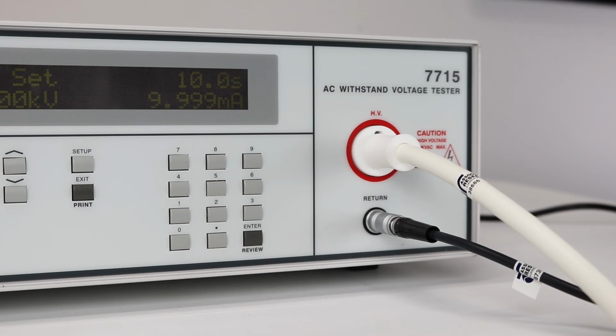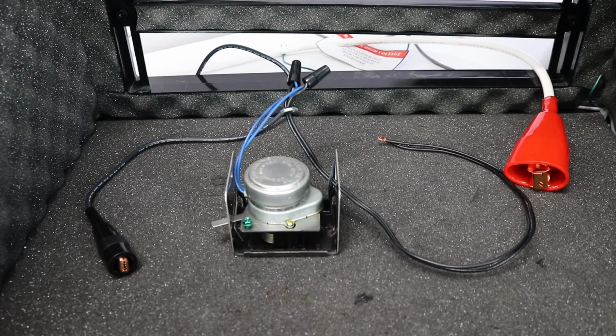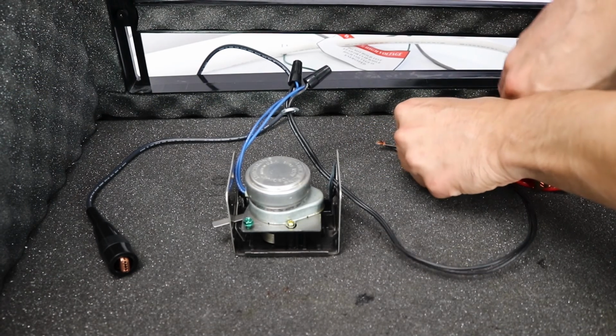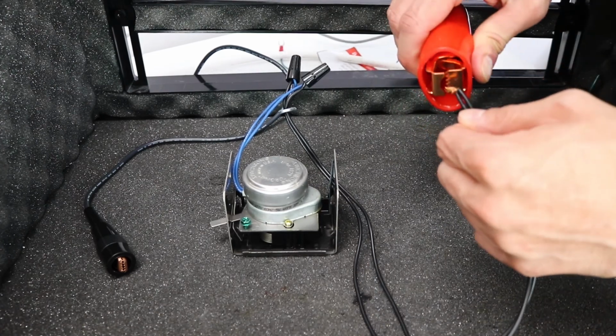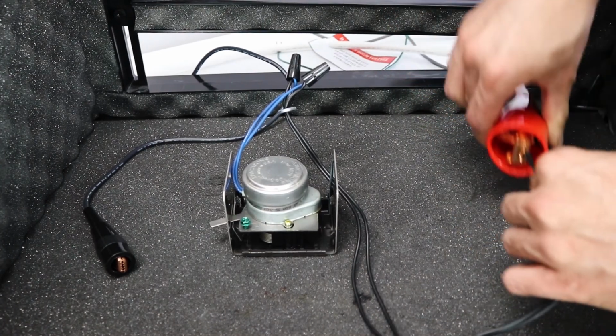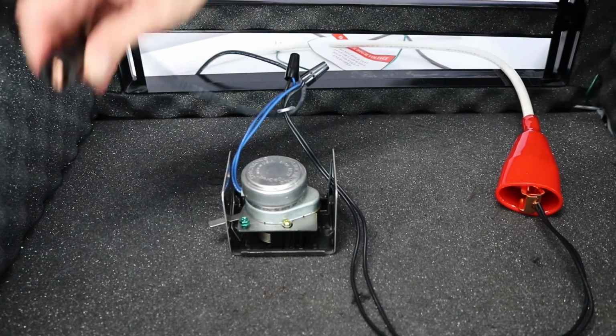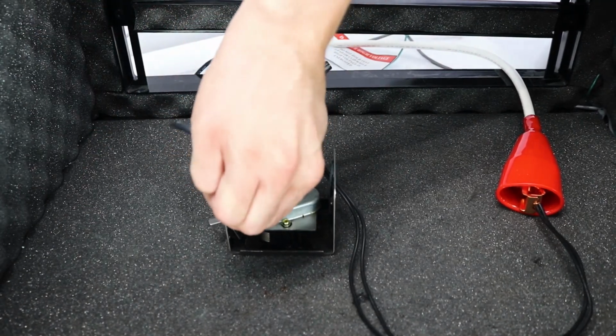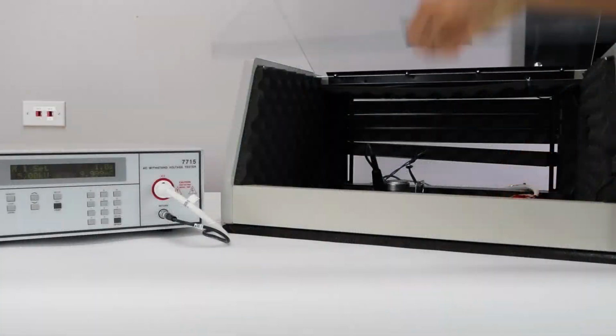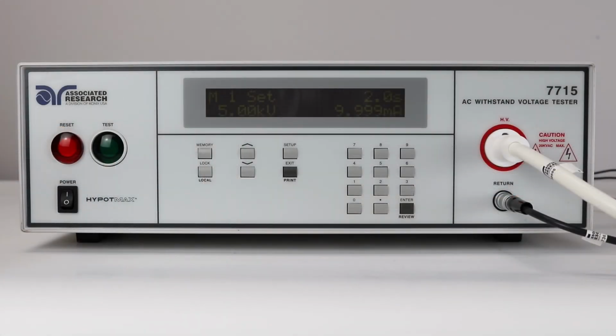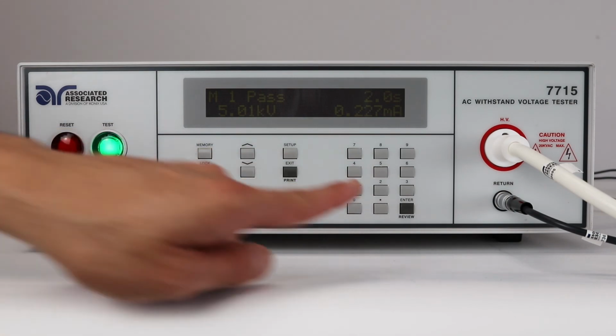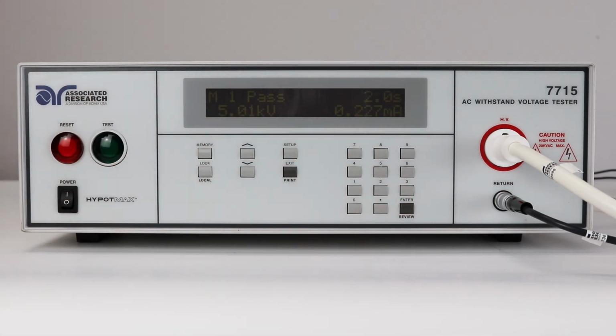Once all these connections have been made, you can now connect your DUT. To connect the DUT, clip the high voltage lead in the mains conductor of the DUT. In this case, we're shorting the line and neutral wires, which are the 2 black wires, to the high voltage lead. Next, connect the return lead to the chassis of the DUT. Close the DUT enclosure door, stand back, and press Test button to run the test sequence. Press the Enter key at the end of the test sequence to view your test results.